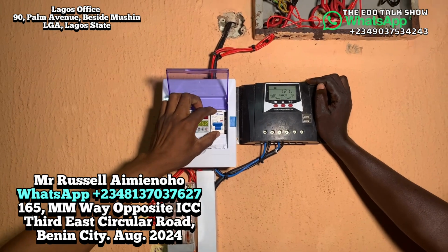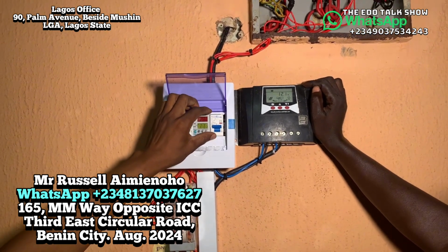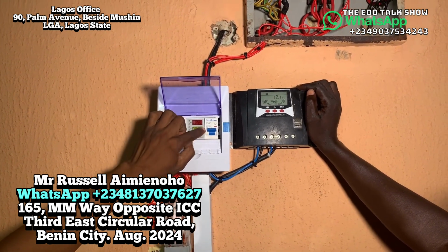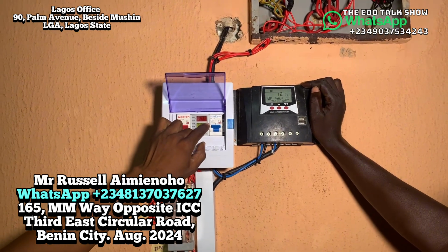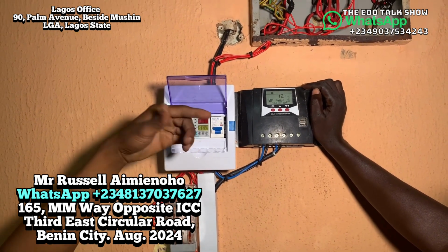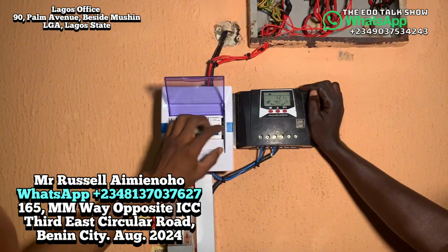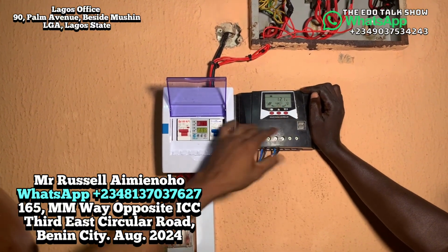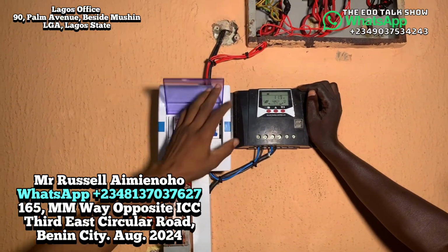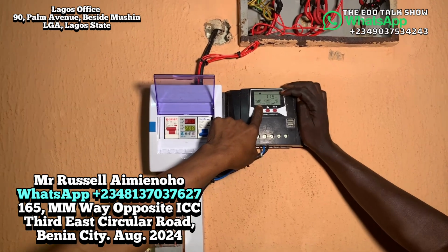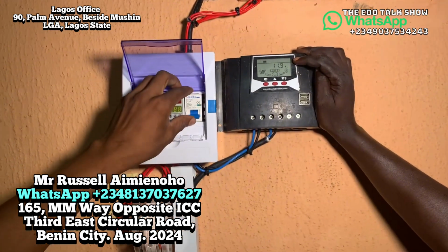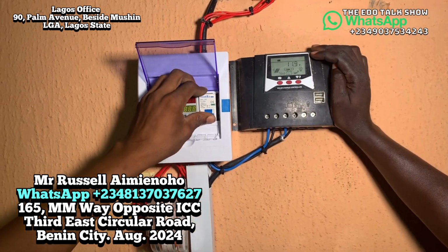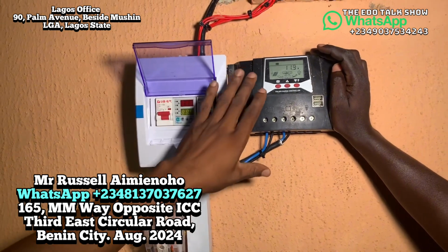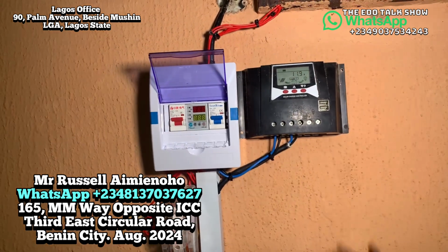Now this blue one is the DC breaker, also 125 amps. If there's a spark from the panel, instead of damaging the solar charge controller, it will go off by itself, stopping the panel from charging. So it protects the solar panel, the charge controller, and also the battery.